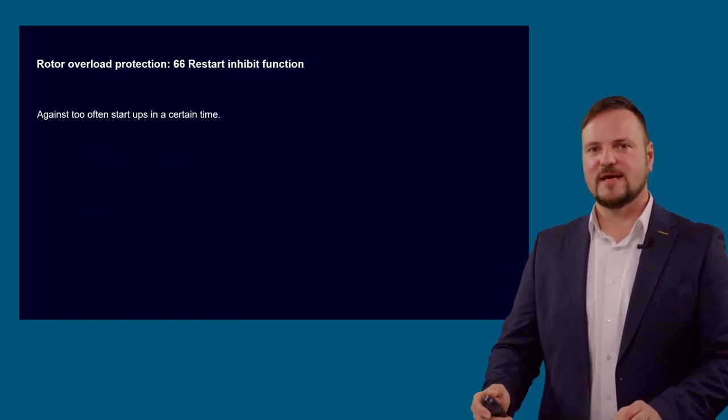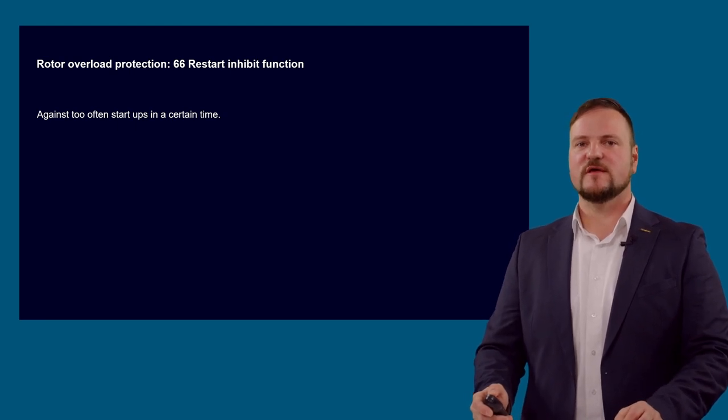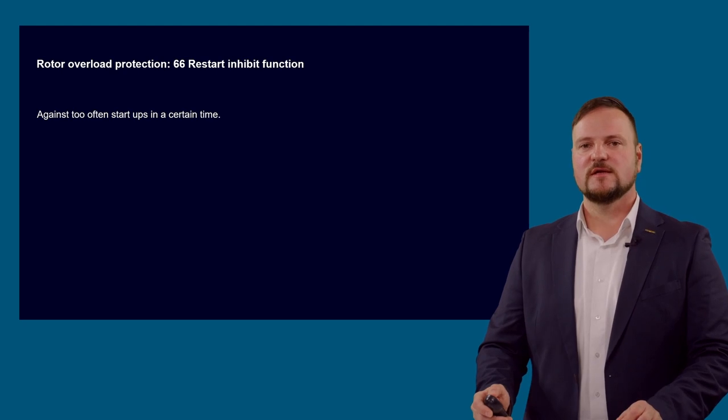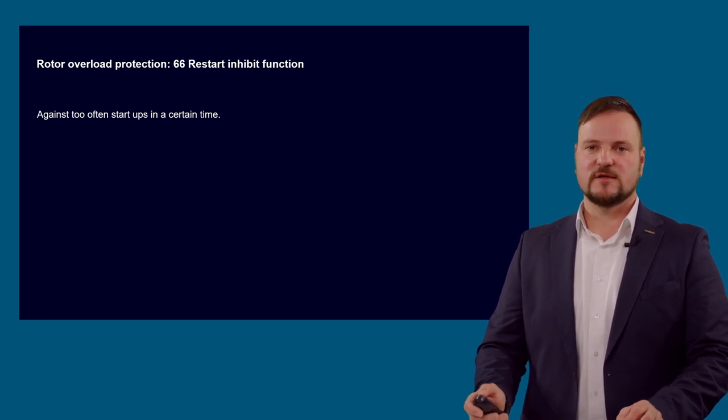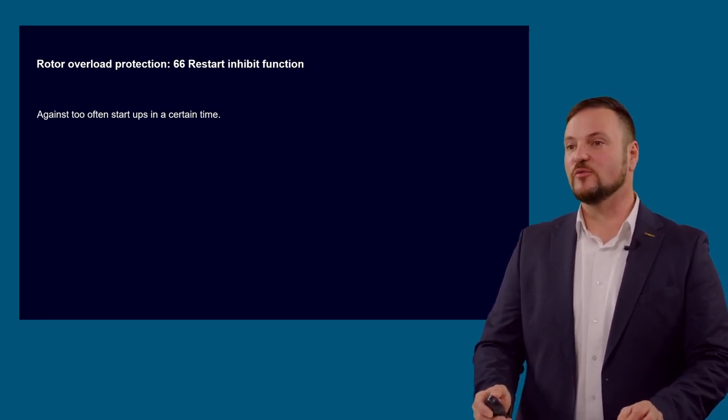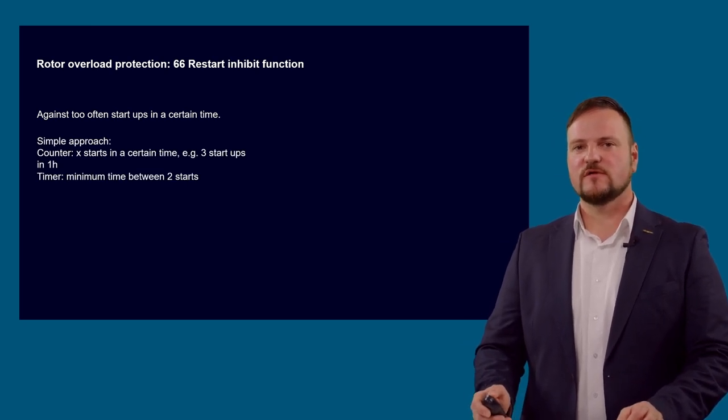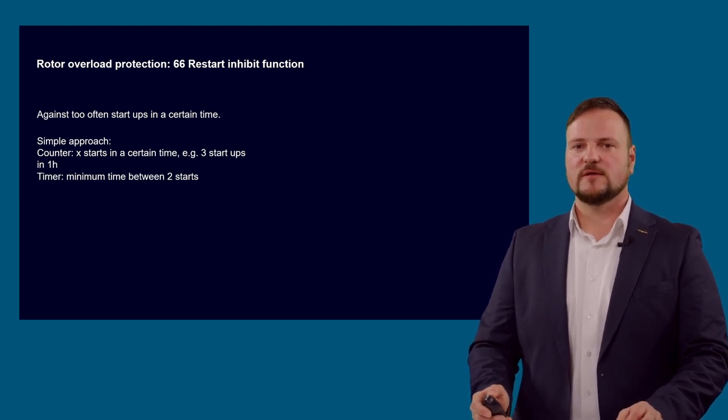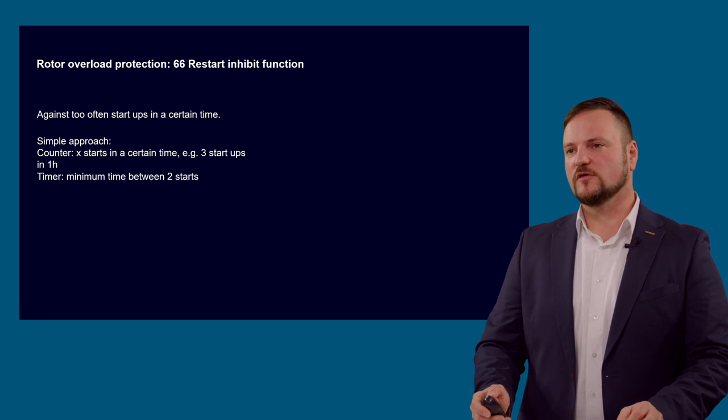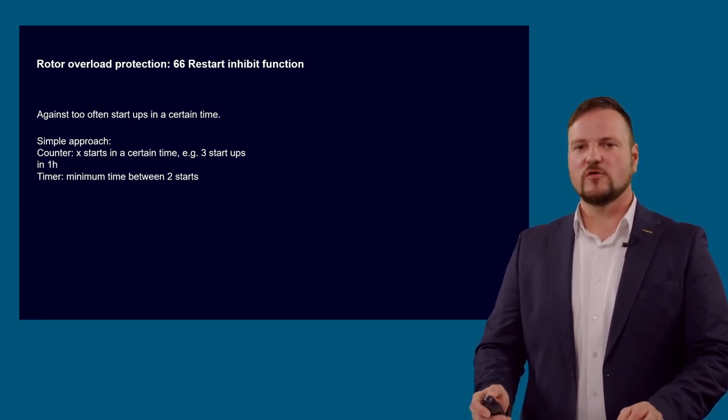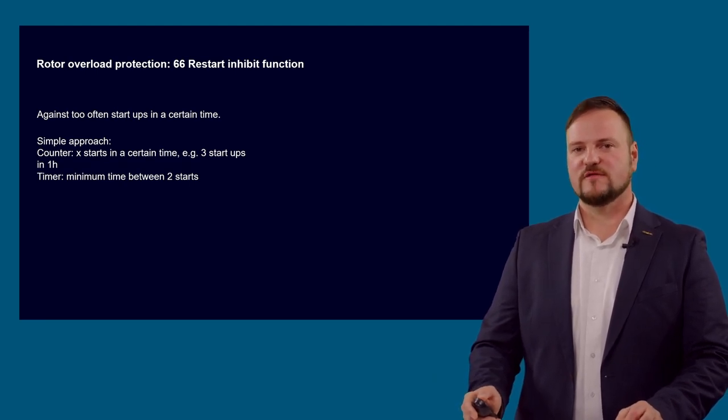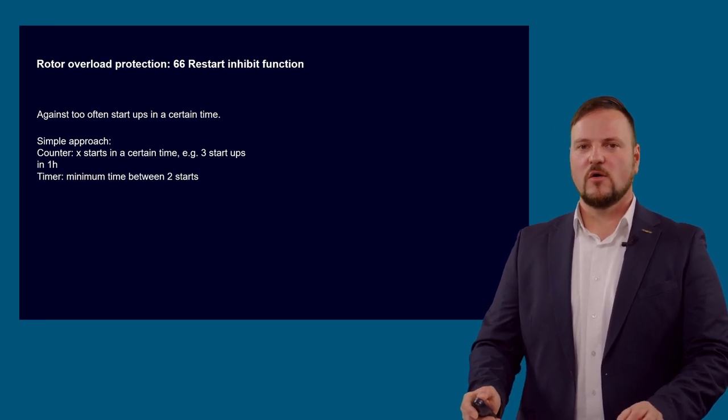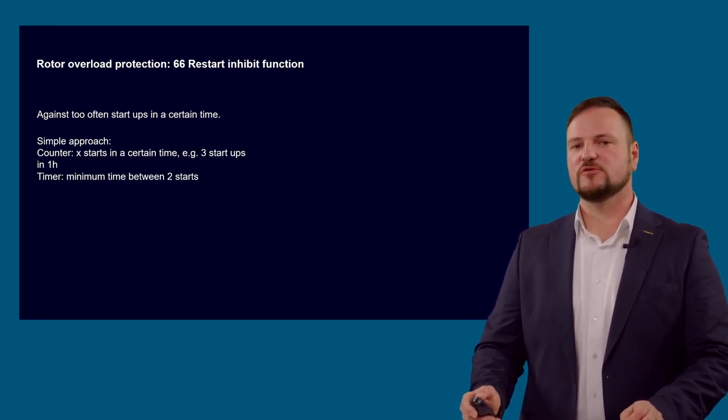The next slide is related to the restart inhibit function. The rotor is extremely sensitive during startup because the stator currents in this period are relatively high. Therefore, we have two protection functions, the restart inhibit function, and later discuss the starting time supervision. The restart inhibit function monitors that not too many starts happen in a certain time, so that the rotor has time for cooling down and is not overheated. In some cases, the given motor data describe a simple approach, like a certain number of starts in a certain time, for example three starts in one hour. Or a certain minimum time must be guaranteed between two ongoing starts.